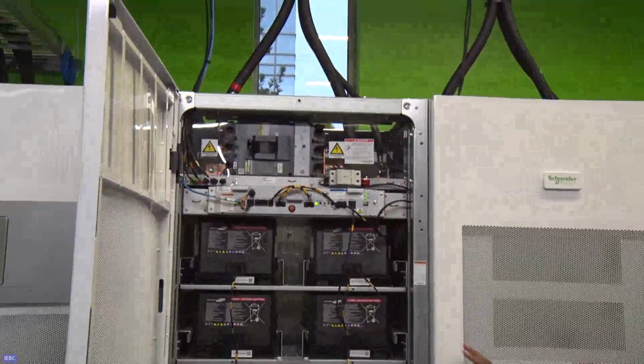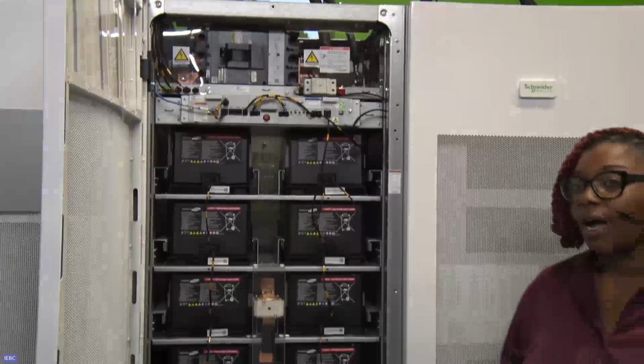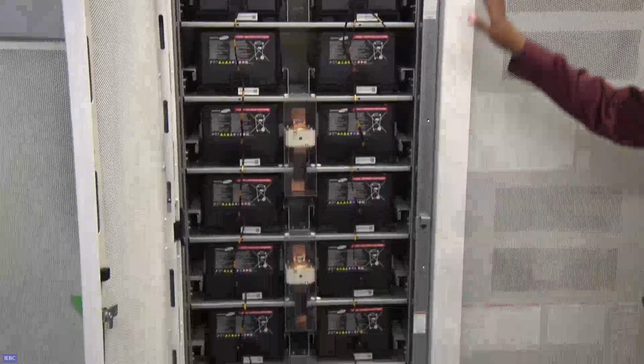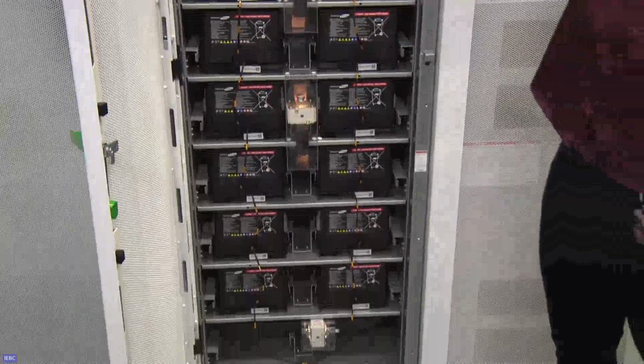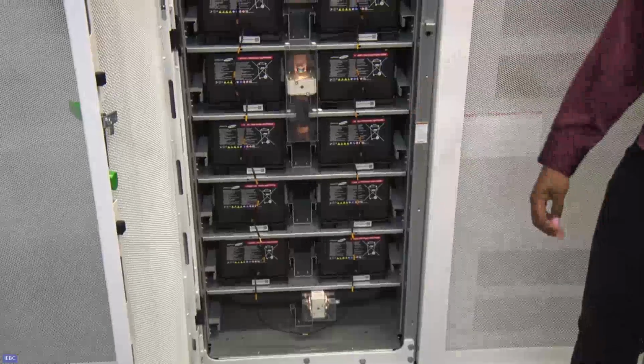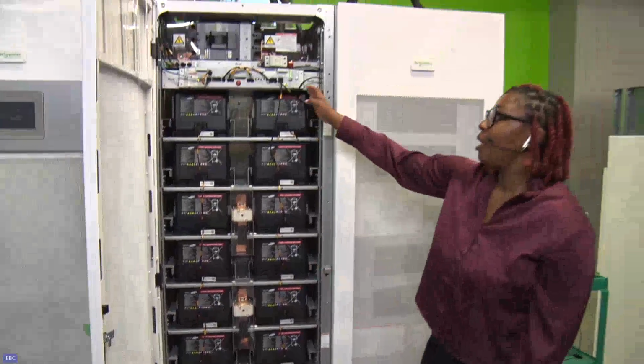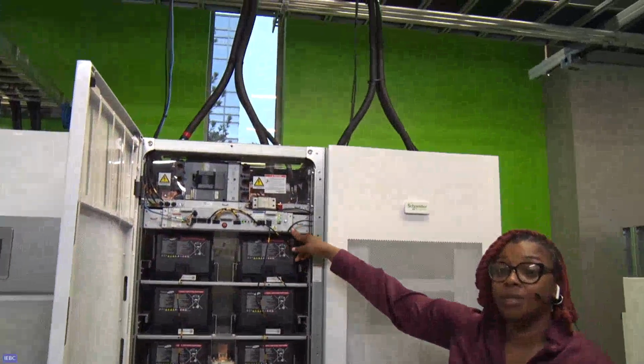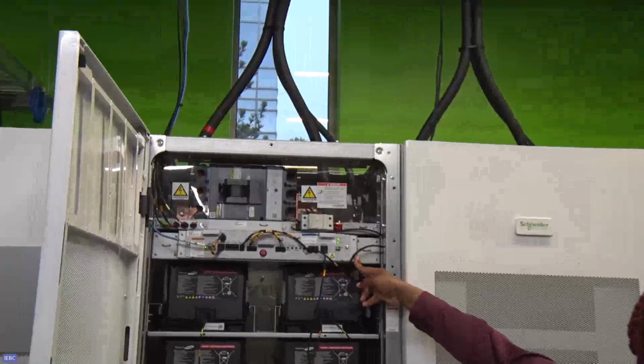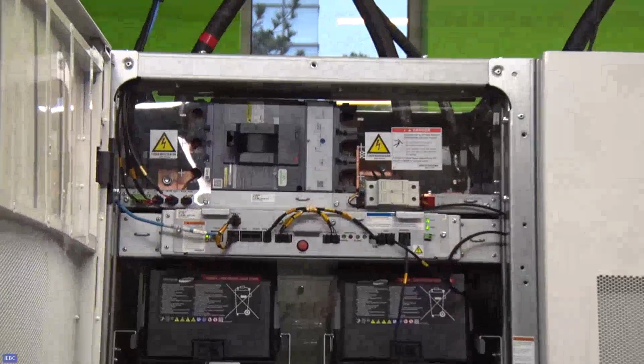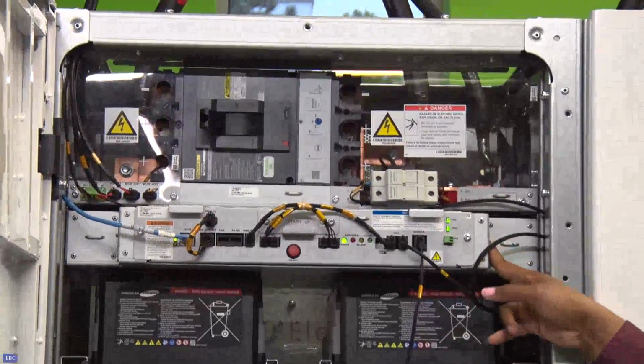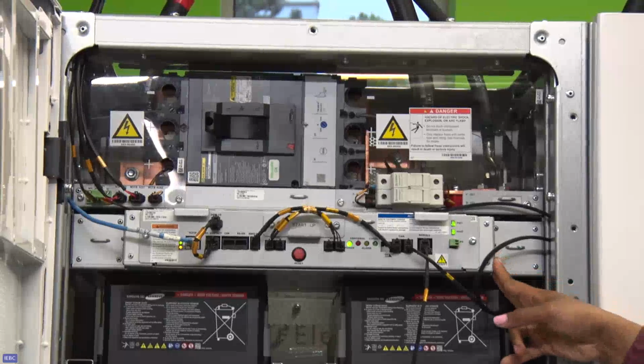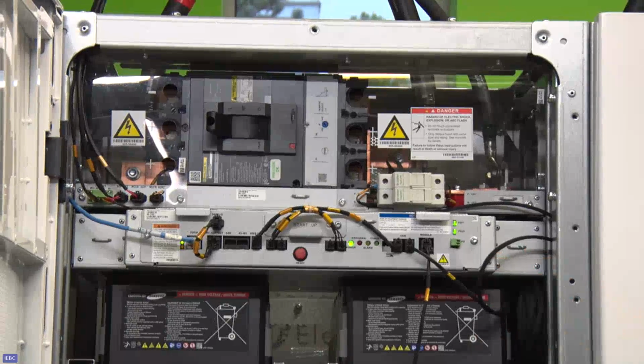This here is a string of 16 lithium ion batteries. There are 4 fuses, one behind here, and then 3 in line. These are all for safety. Here we have our battery management system. These are mandatory with lithium-ion batteries. And this is powered off of the DC bus. What that means is as long as our UPS is running, so is this battery management system.